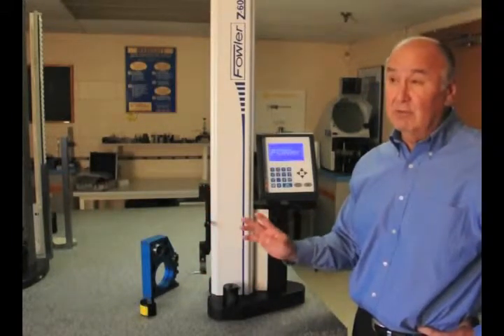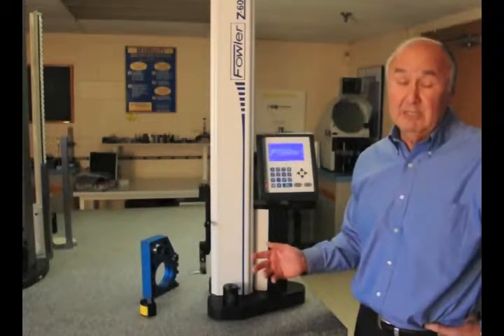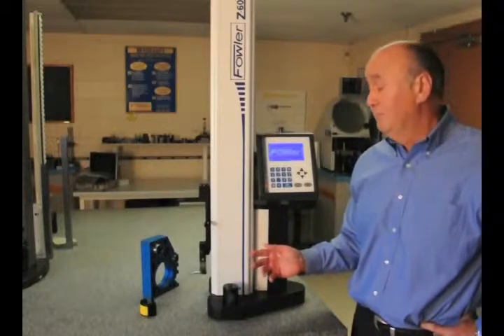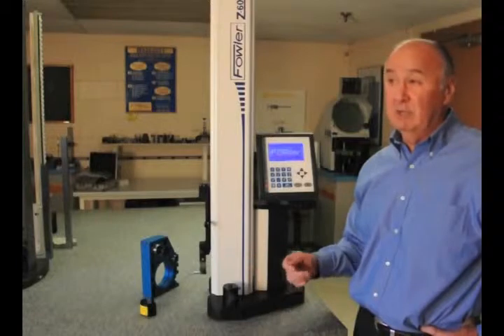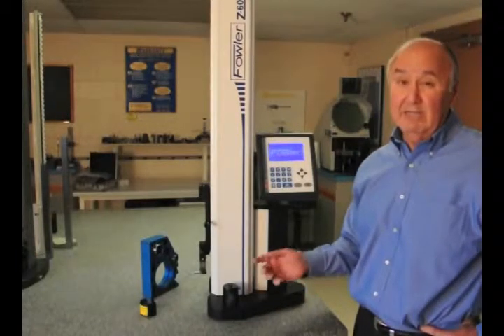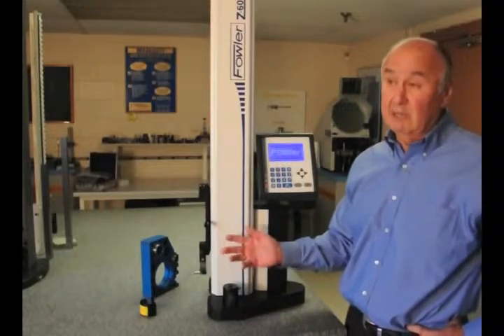The accuracy over the 24 inches is a little over 2 tenths. The repeatability is about 2 microns or 80 millionths. The formula for the accuracy is 3 plus length travel divided by 250.